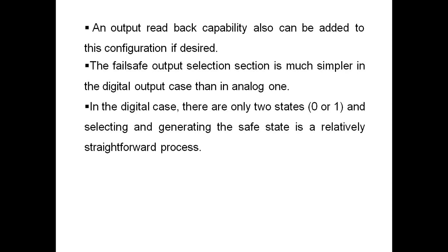In this configuration, if desired, the fail-safe output selection is much simpler in the digital output case than in the analog one. In the digital case, there are only two states, 0 or 1, and selecting the fail-safe state is a relatively straightforward process. Thank you.